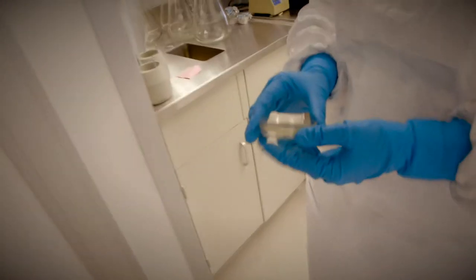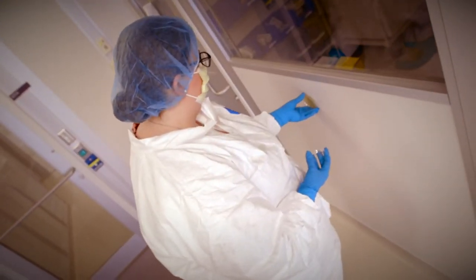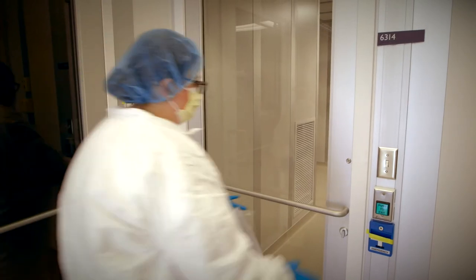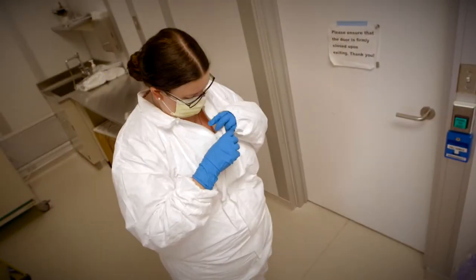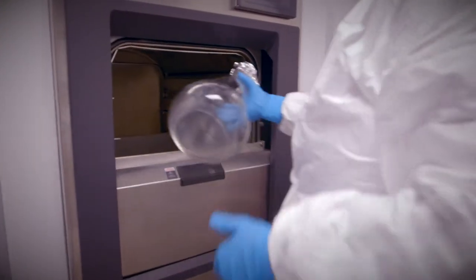Additionally, the facility is subject to a cleaning regimen that includes equipment, floors, walls, and ceilings. There is a changeover cleaning procedure which takes place between patients to prevent cross-contamination. Once work is completed, the technologist exits the clean room through the degowning and decontamination room, removes the PPE, and places it in the biohazard trash, which is autoclaved before removal from the facility.